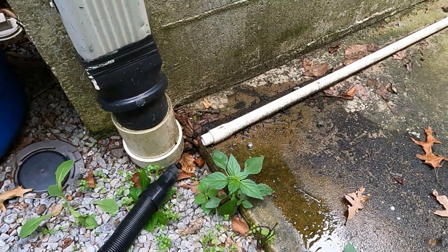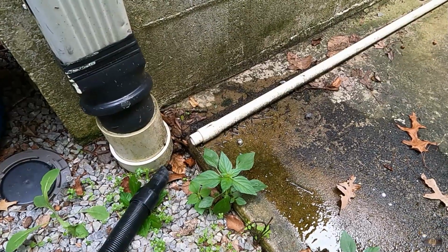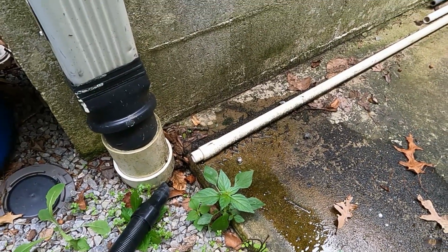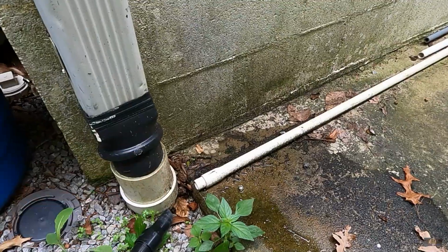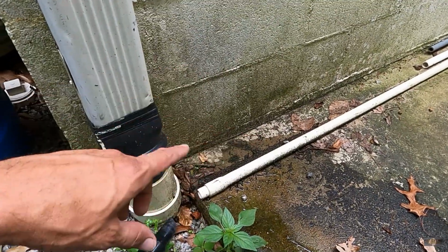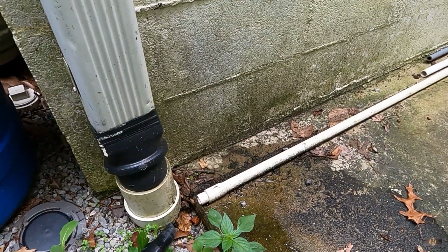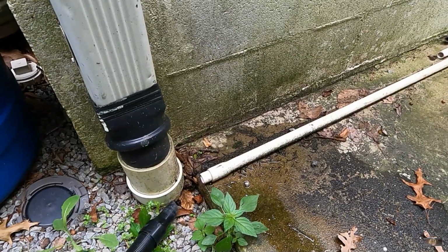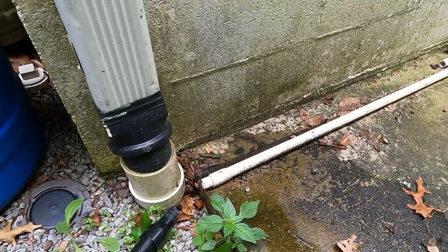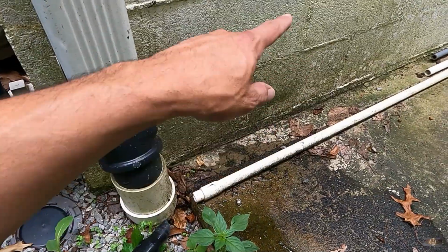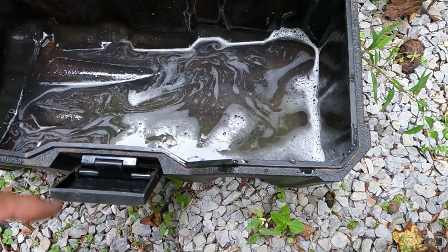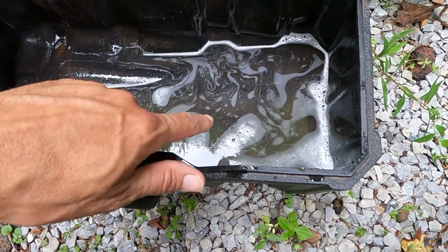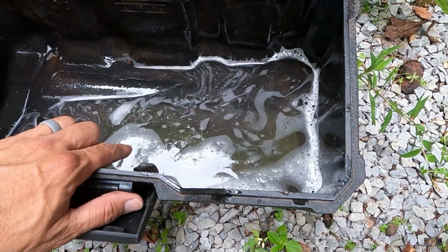I'm going to give it a suck, and I've got about a quarter gallon to go ahead and reprime the trap. I've got the vent capped, and I took the 90 off of it, put a cap on it, and then put a cap on the clean out for the P-trap. So when I pull this vacuum, it's going to pull through the whole line, through the trap, and all the way into the coil. So I sucked the P-trap clear as well as the drain line, and you can see this is more water than what's in the P-trap.